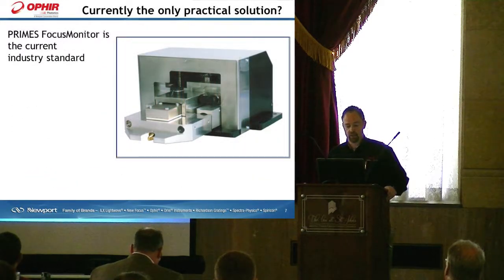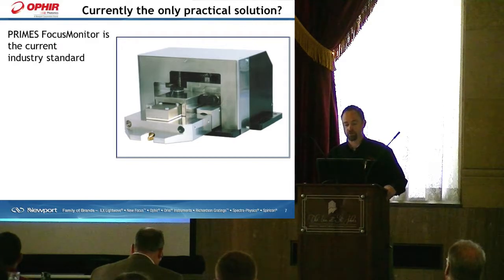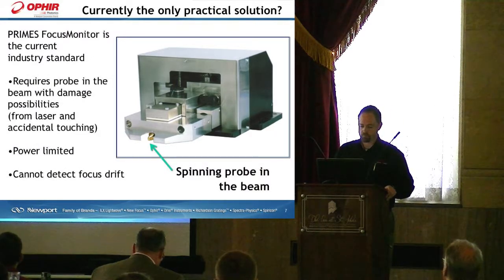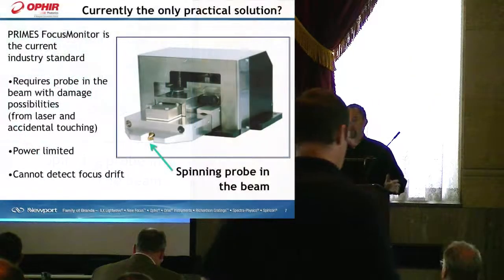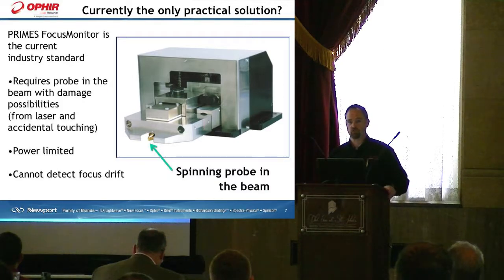The PRIMES FocusMonitor is the current industry standard and has certainly served this room very well in the past. It does give a lot of information about the beam and is a good product. However, there are some problems with its use. One, it requires a probe to impinge on the beam. As laser powers and power densities go up and up, the limitations of the device are clearly seen — there are possibilities of damaging it, and touching that spinning probe can affect your measurements. It is power limited, and it cannot detect any focus drift or shift within the focus spot.